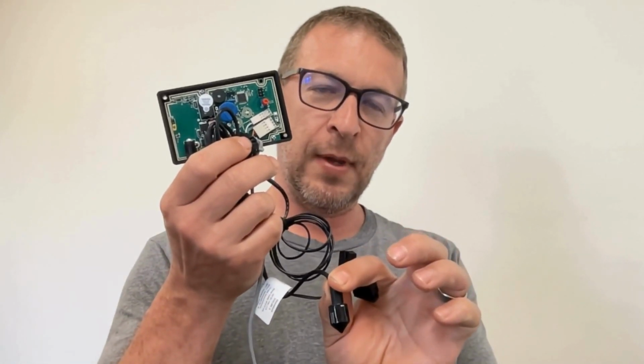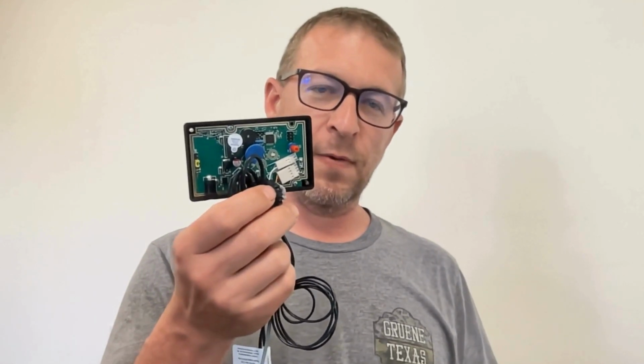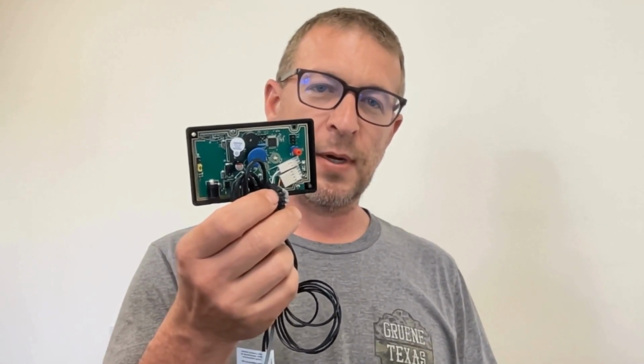So we've essentially covered the main error codes: too high, too low, water damage, which is too high and too low flashing. I should point out that the green level light might be on with that as well. If the optic sensor is in water, you will get a green level light with the water damage indicator, but the one thing you won't have is all 4 lights. And then if all 4 lights are flashing on and off in a slow pattern, that points to an overload, which is usually a bad pump or wrong power supply connected by mistake. Always check that the power supply is correct. It should be 5012.010. It's 1600 milliamps, 12 volts.